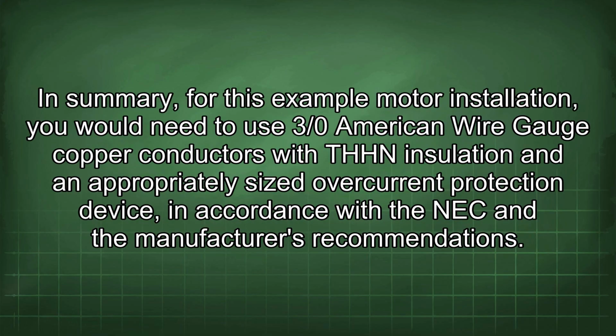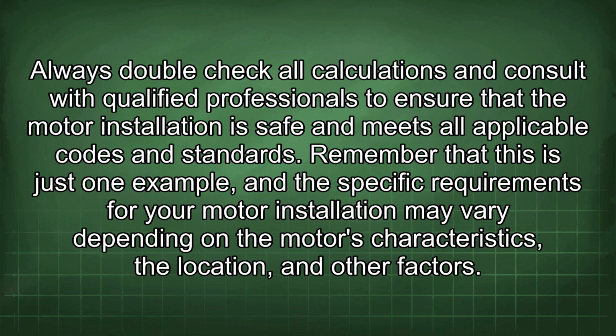In summary, for this example motor installation, you would need to use 3/0 American wire gauge copper conductors with THHN insulation and an appropriately sized overcurrent protection device, in accordance with the NEC and the manufacturer's recommendations.